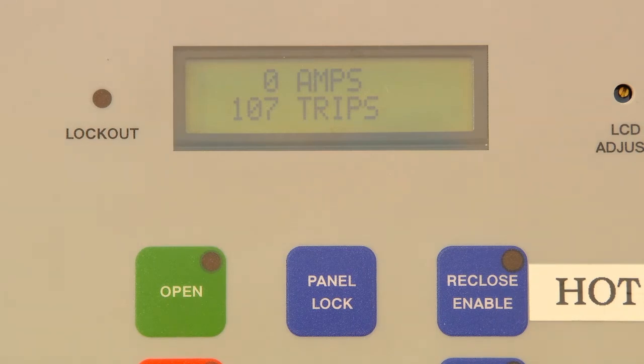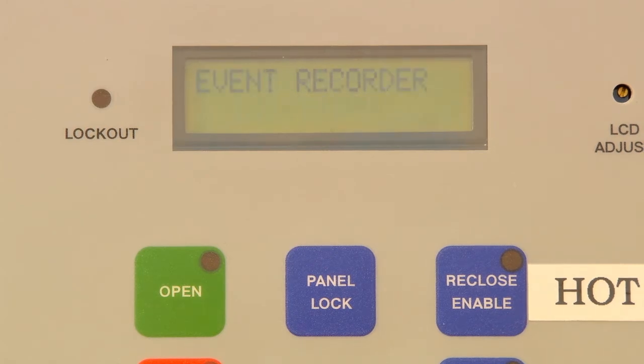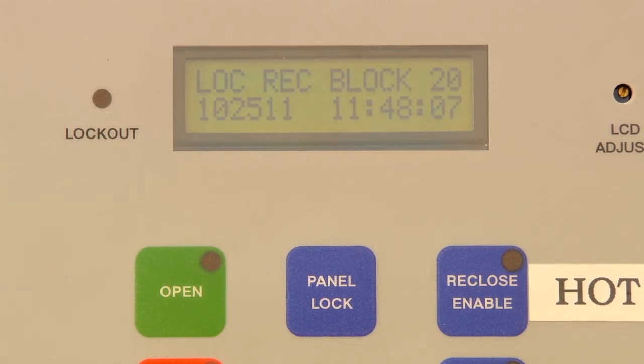This screen displays both amperage as well as the number of trips on this unit. Pressing the Event button will display the most recent event, including date, time, and amperage. In this case, a manual trip or a block of the actual reclose. You can move to the next event by pressing the down arrow. Proceeding down farther will display exactly what's happened for each one of the events.